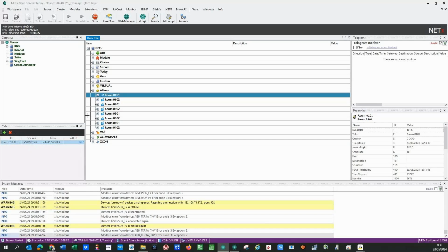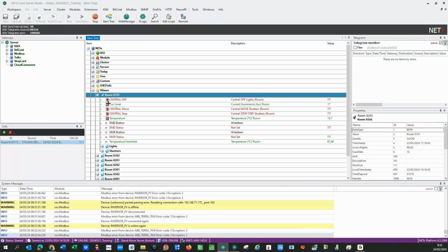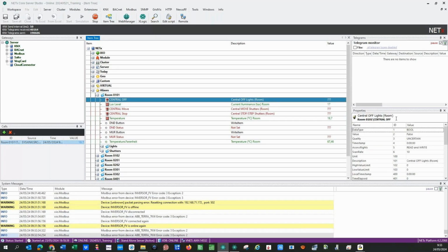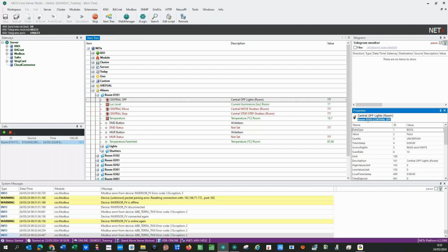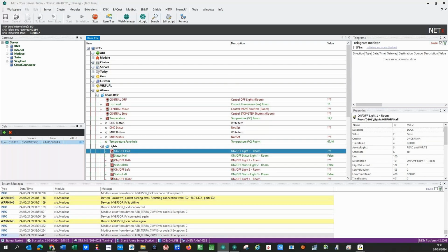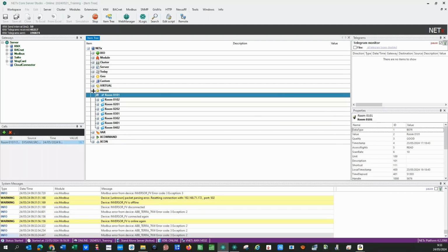We were thinking about the proper item structure, mixing different technologies using the alias, in order to have all these items easily recognizable. Easy to recognize because of the number of the floor, the number of the room, or whatever element, or the identification of the circuit, for example. Three different things can change: number of the floor, number of the room, or the circuit name. These three things can also be used with the variables concept.